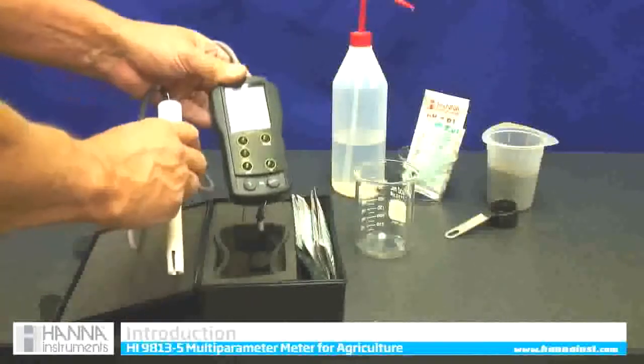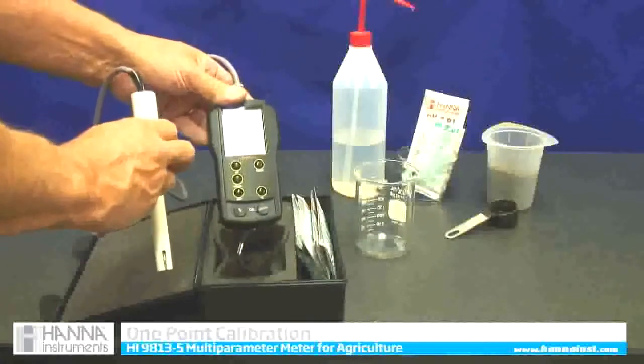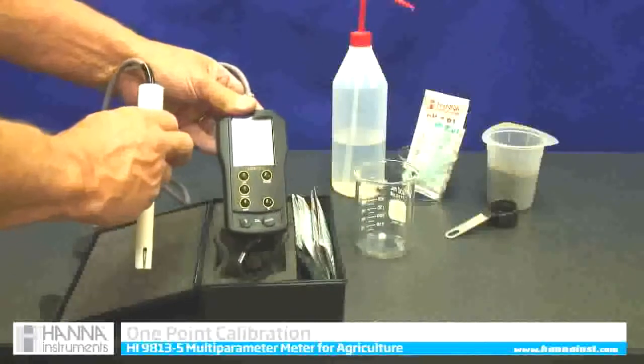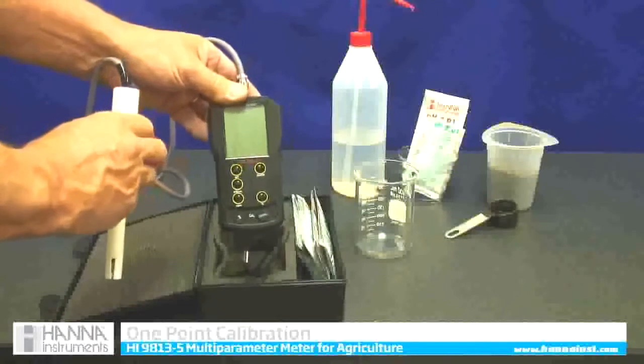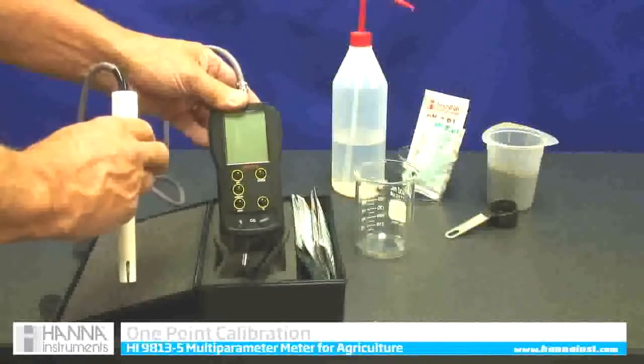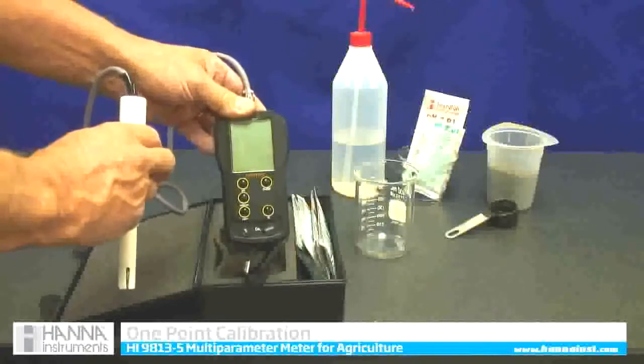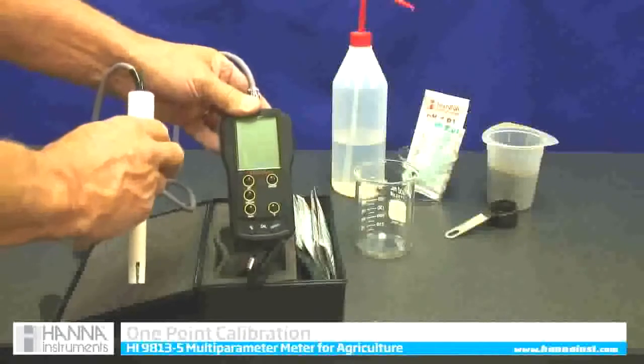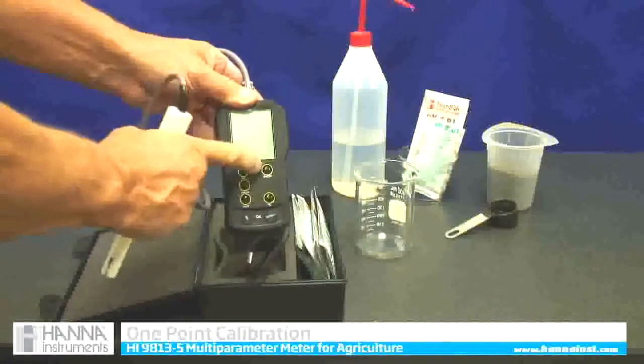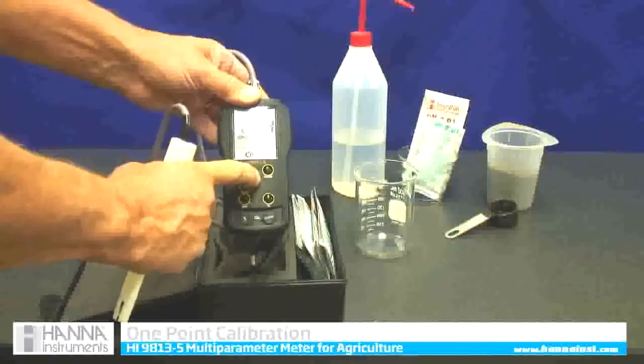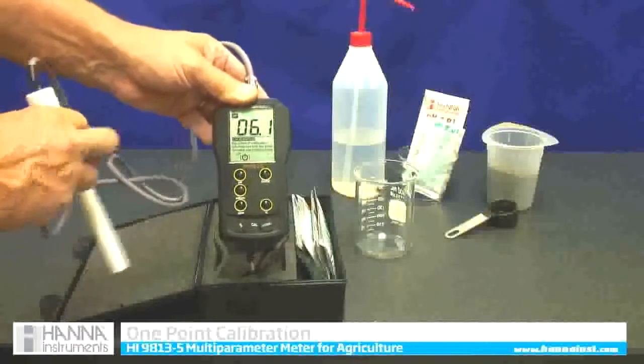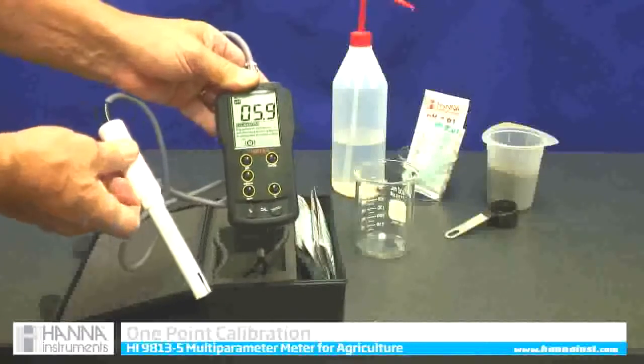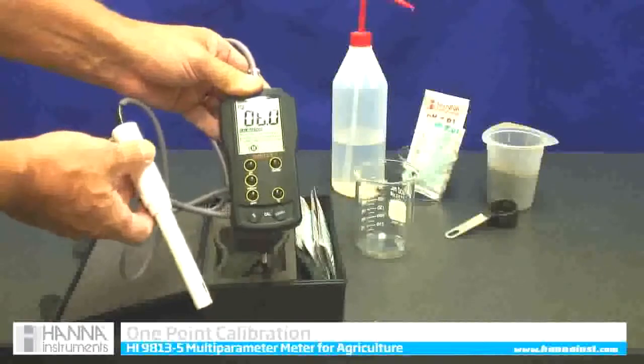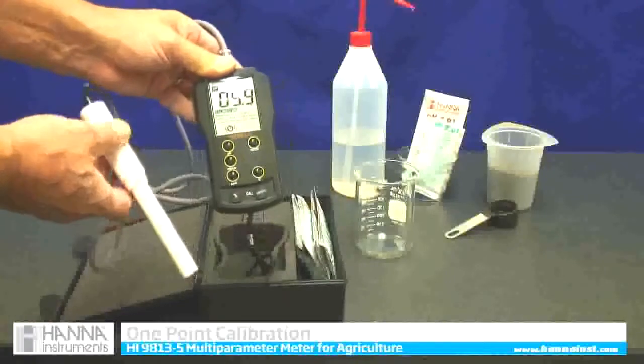It's important to calibrate it, especially when you get it, because we don't know how long it's been out of calibration. So check it for calibration. It's extremely easy. On this one, all we have to do is turn it on with the on-off button. Then we're going to put the probe in a known calibration solution. It doesn't have to be any one in particular. We are going to use pH 7.